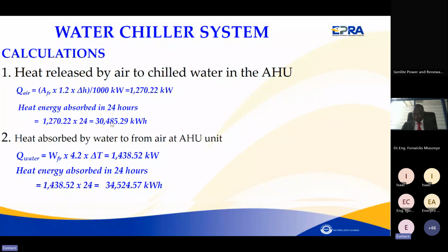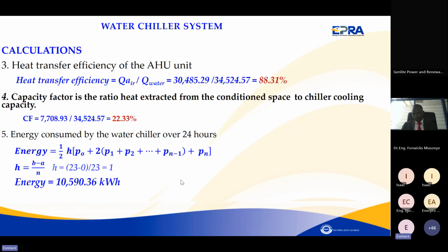The calculations I did: the heat released to the chiller, chilled water, is 30,485 kilowatt hours. Heat absorbed by water within 24 hours is 34,524 kilowatt hours. We found that the efficiency ratio is 88.31. The capacity factor of the whole system is 22.3. The energy consumed in the facility is 10,000, by the chiller it is 10,590.